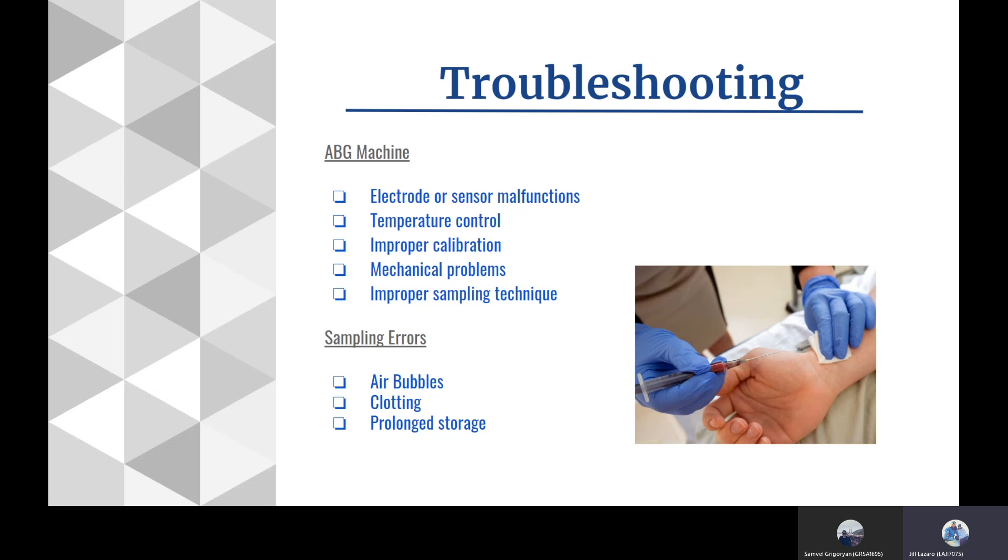When we go into machines, there are a couple of things we can do to troubleshoot. We oftentimes have errors we need to figure out. In regards to troubleshooting, the first is ABG machine errors. Common issues include electrode or sensor malfunction, improper temperature control, improper calibration, mechanical problems such as something not working or jammed up, and improper sample techniques.